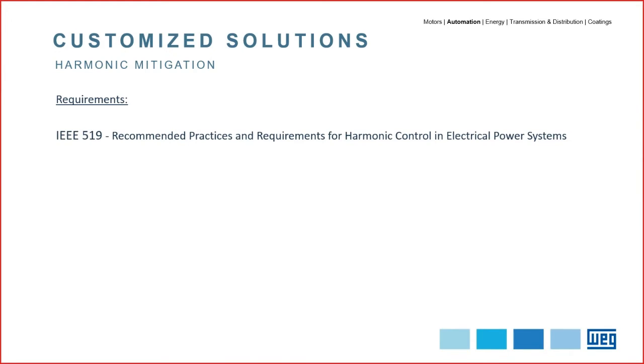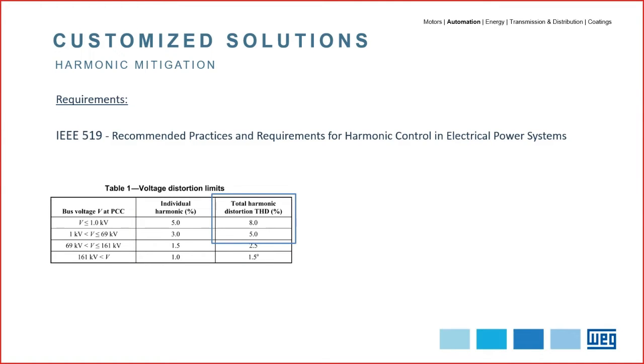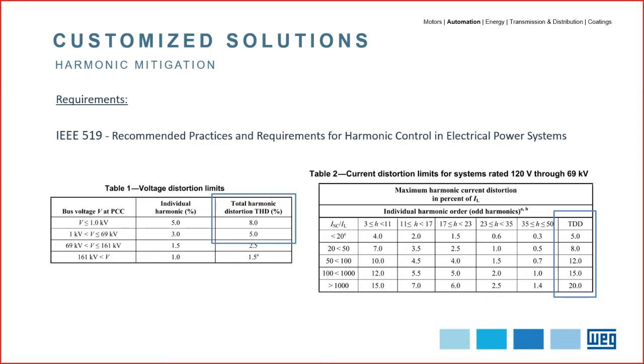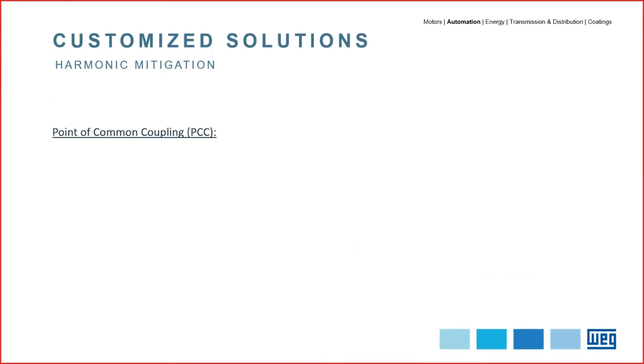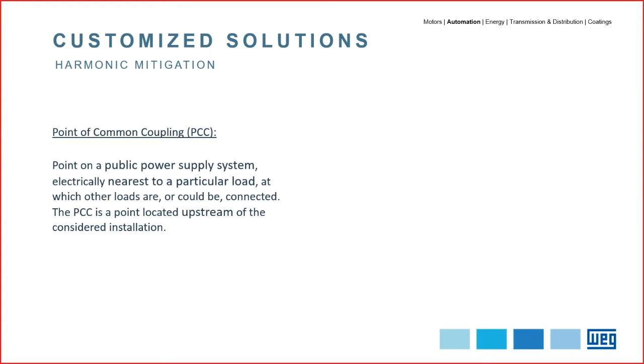So the IEEE 519 is the most accepted international recommendation about harmonics and establishes criteria on acceptable limits for harmonics in the electrical power system. These limits consider the system voltage level as in table 1 and the relation between the current load and system short circuit capability as listed in table 2. Then, according to the recommendation, these values must be verified in the PCC, point of common coupling. And what's the PCC? We can define it as the point on a public power supply system electrically nearest to a particular load or at which other loads are or could be connected.